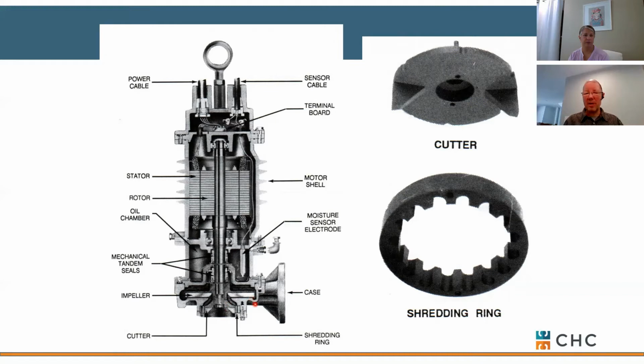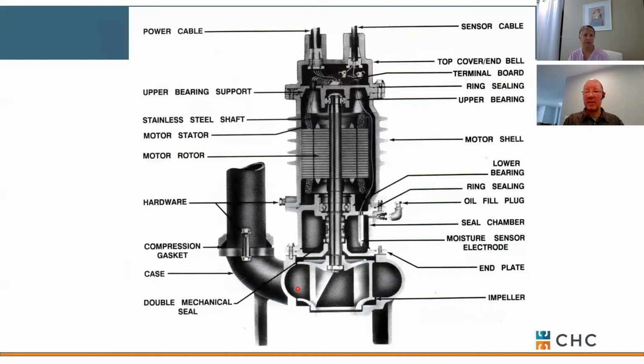We tend to use a lot of grinders if we're trying to get into a high pressure return, maybe an elevated return where you need quite a bit of pressure. Maybe an undersized distribution line where you need to get 2-inch solids into a 1.5 or 2-inch main. Okay. On price between the two, the grinder is actually quite a bit more expensive than a pump that can pass full size particulate. It might be a little bit more on maintenance as well.